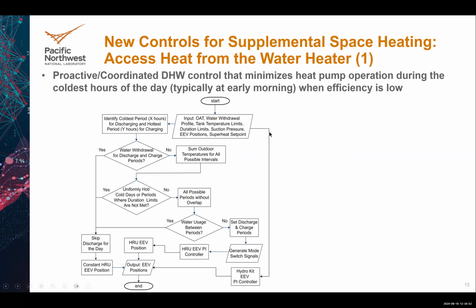So basically, you start by discharging your tank first when the outdoor temperature is very cold. Then you charge your tank back when the outdoor temperature is hottest during the day. But the issue is, since you also need to use the hot water, right? You need to guarantee there is no water withdrawal when you discharge or charge your tank. Meanwhile, during your discharge and charging period, there also needs to be no withdrawal. Otherwise, you cannot guarantee your hot water tank temperature. So that's why we build a flowchart to show the control process.